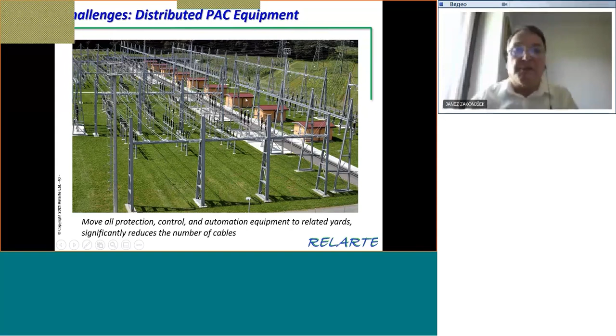And if you look today, that means we could maybe discuss still the possibility to have such relay in the same way as it was before, so that it will provide very good communication, a very fast operating time. It can be located in such house. It will go to station bus over 61850, and it can send out also, for example, sampled values or some other digital signals over to the external process bus.